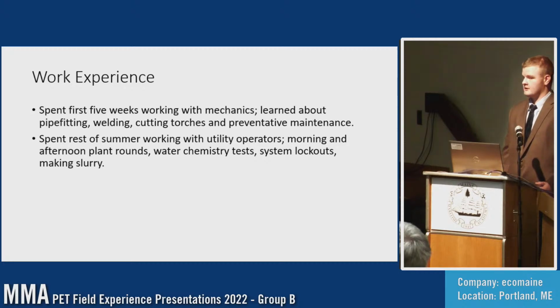Another thing you're constantly doing as an operator is checking on the ash extractors. If those plug up, which I saw multiple times this summer, it's no fun - they get real hot and it can cause damage to the boilers. So you're constantly checking your ash extractors for any plugs and staying in contact with the control room.